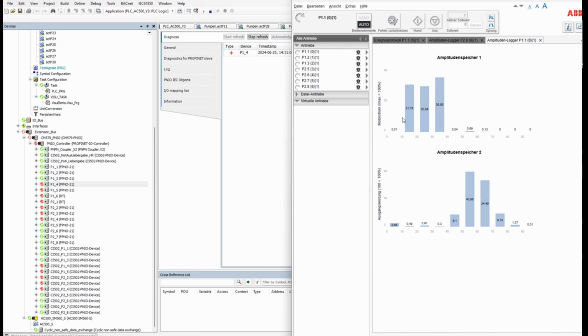And it's kind of a histogram which shows, across this whole year, where this pump has been working most of the time. So if you look at the output power, most of the time the pump has been working between 50 and 60% load. Very, very seldom it worked even between 80 and 90%, and almost never at 100% of its load.